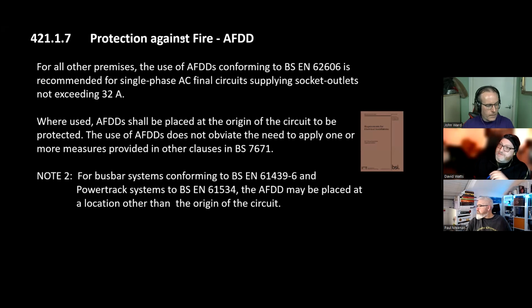I expect a few people have had this asked a few times, so let's just discuss it. Ring final circuits, do AFDDs work fine? Yeah, they do. Well, it depends on what kind of fault you've got. If you've got a parallel arc fault, say between line and neutral, it will work just the same as on any other circuit. If you've got a break on a single conductor, say the line, then it won't. But on the other hand, if you just break a ring, there's going to be a very tiny current there in most cases anyway. So there isn't actually anything to detect.